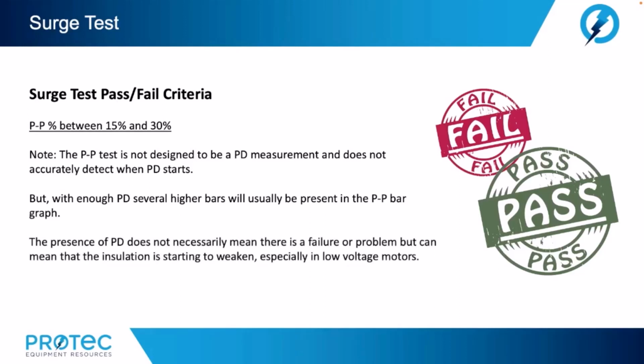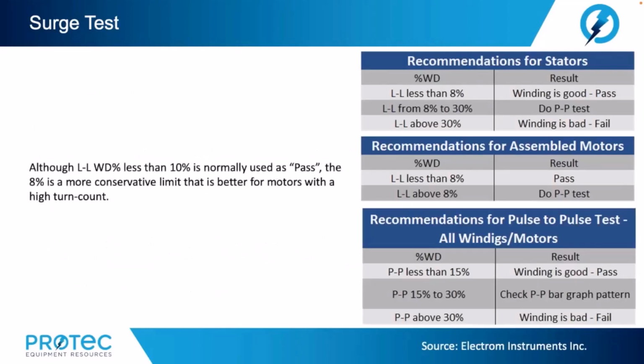The presence of partial discharge does not necessarily mean there's a failure or problem, but can mean that the insulation is starting to weaken, especially in low voltage motors. Now, around 30% and above, the partial discharge typically turns into an arc. Although lead-to-lead WD percent less than 10% is normally used as pass, 8% is a more conservative limit that is better for motors with a high turn count.